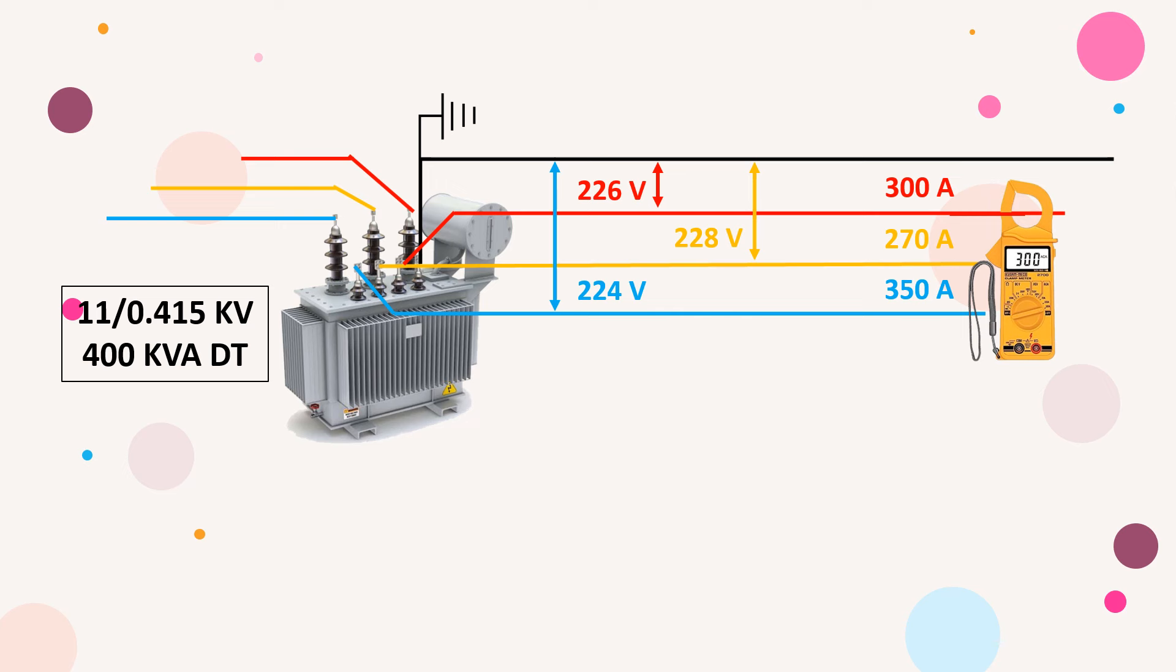The first thing we should be clear about is that to calculate the total power flowing from this transformer, the power factor value is not required at all because the ampere loading you see here is apparent load. It includes the amperes corresponding to both types of load.